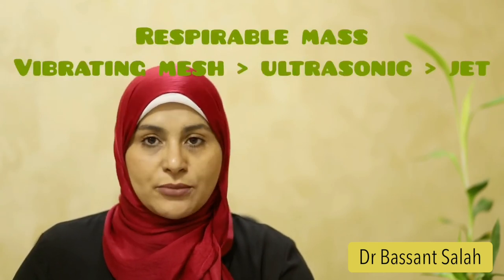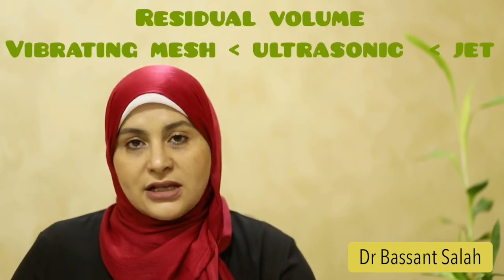So if you compare between the vibrating mesh, the ultrasonic, and the jet nebulizer, which one has more respirable mass? The vibrating mesh has more than the ultrasonic, which has more than the jet nebulizer. As for residual volume, the vibrating mesh has the least, less than the ultrasonic and less than the jet nebulizer, making nebulization time less with the vibrating mesh than the ultrasonic and the jet nebulizer. Also, the ultrasonic nebulizer is not optimum for most medications, as during the nebulization process the temperature of the medication increases, which causes denaturing of some medications such as antibiotics.